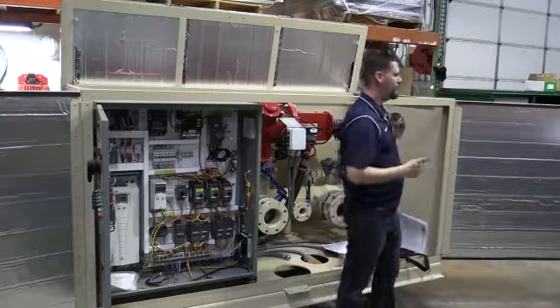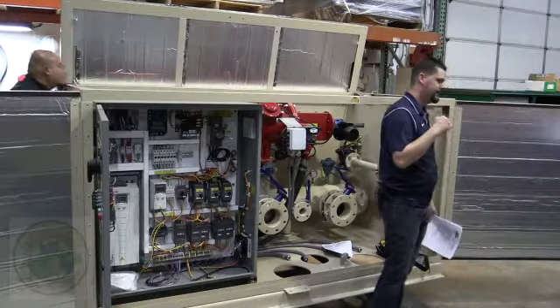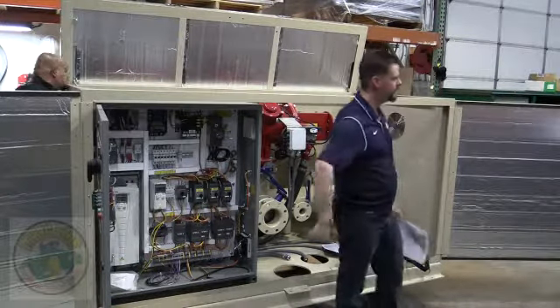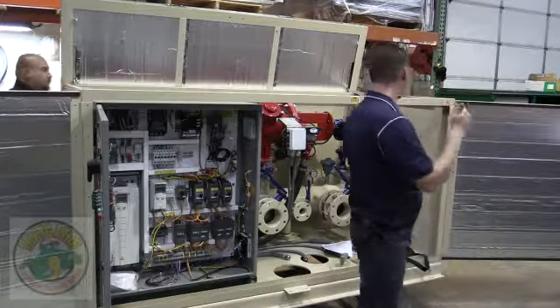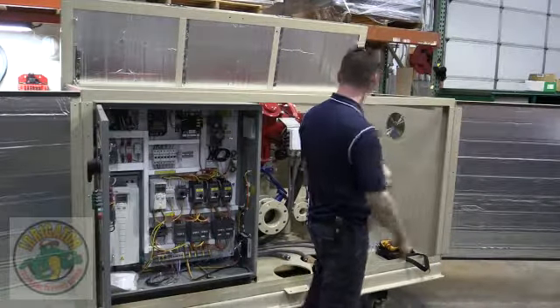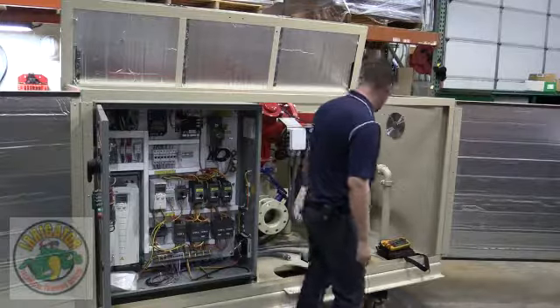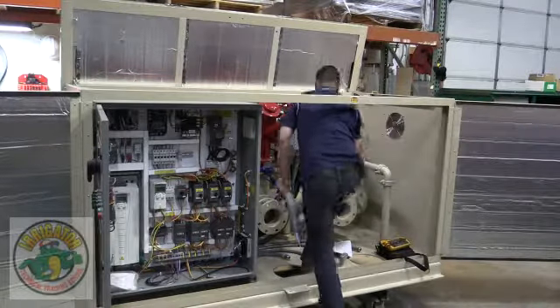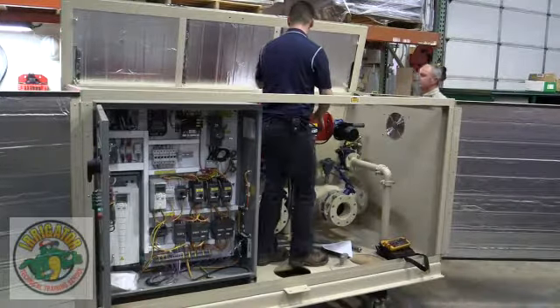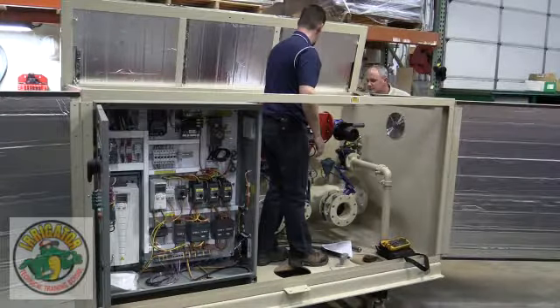So with that one action, you can test the differential pressure input, the valve output—you'll hear the valve open—and both the limit switches, which are pretty easy to access.